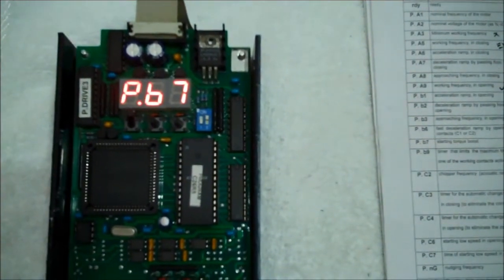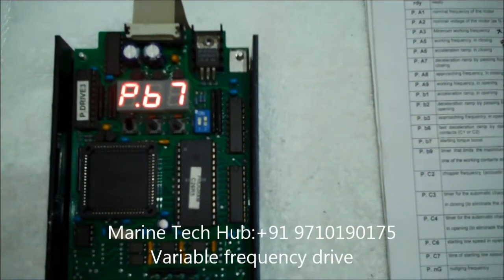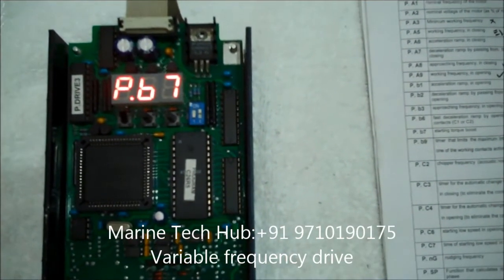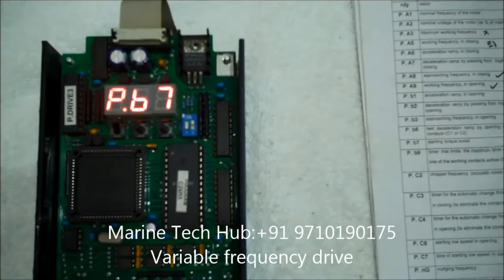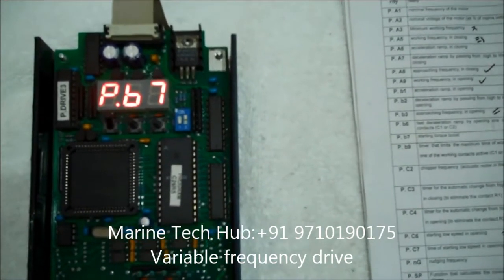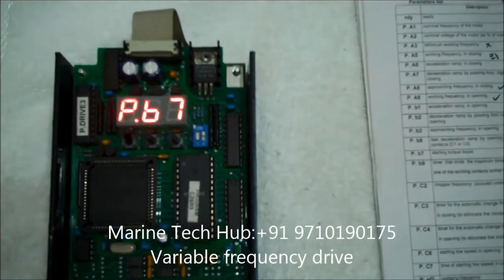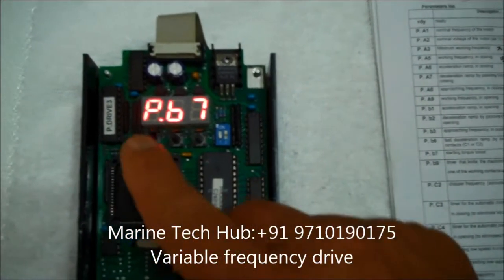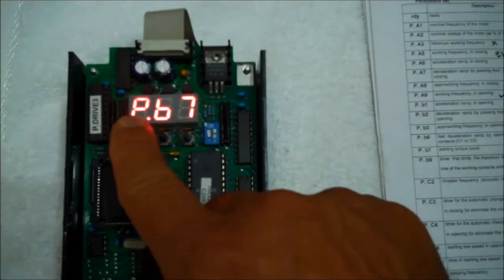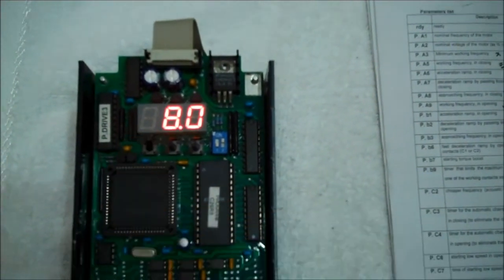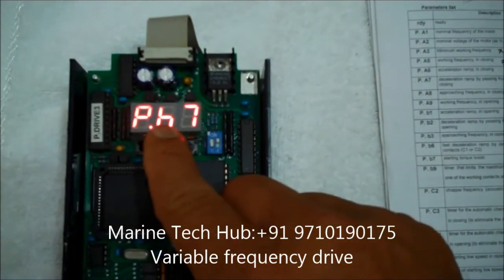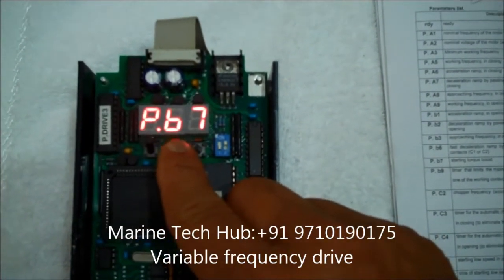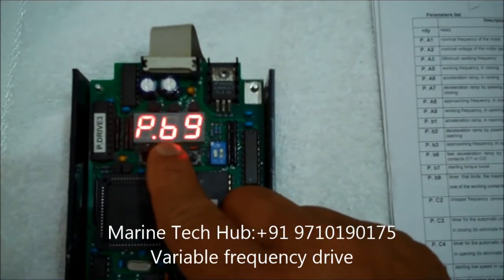Next I will go to the next program, PB7. PB7 is starting torque boost. So this is normally kept around 8% or 9%. I will see how much it is. It is around 8%. So it is okay.